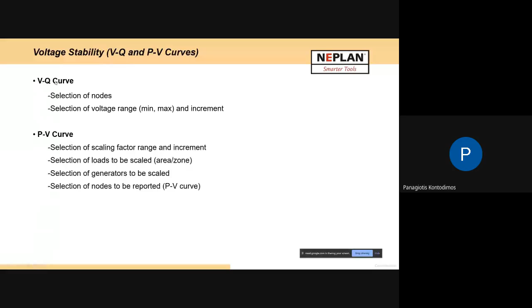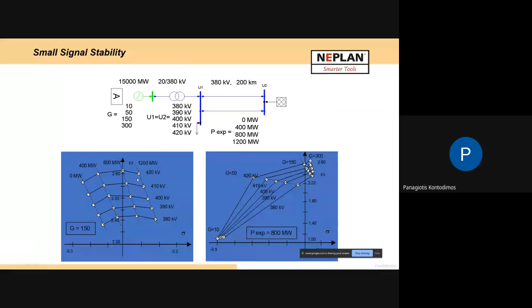There we can make different kinds of sensitivity analysis, so we can see that this bus bar, for example, this node, is mainly responsible for the voltage instability. Then we do a sorting, and we can see that this one doesn't participate in voltage stability. Therefore, we need to concentrate on these bus bars in order to improve voltage stability, as an example. Here are some examples of the results we are getting.